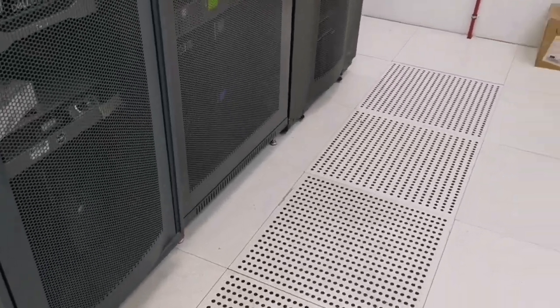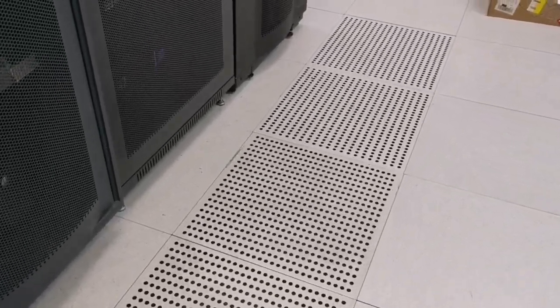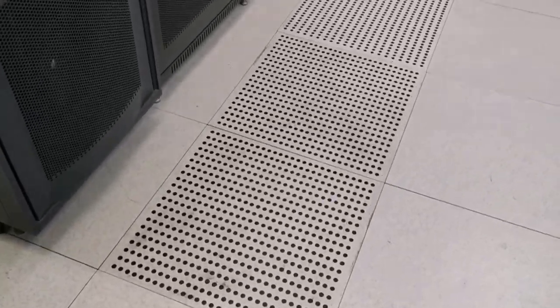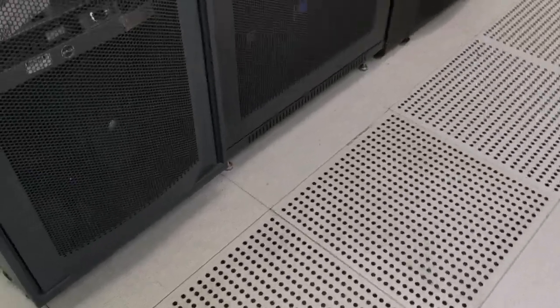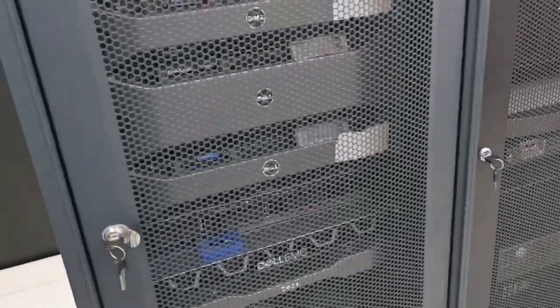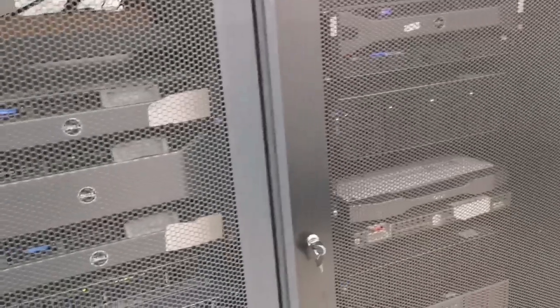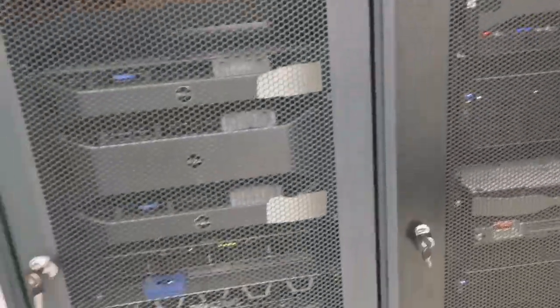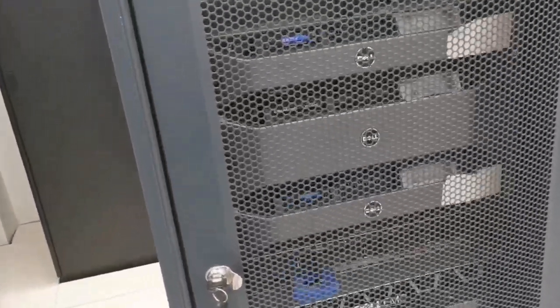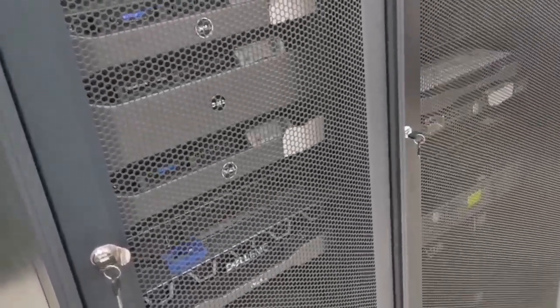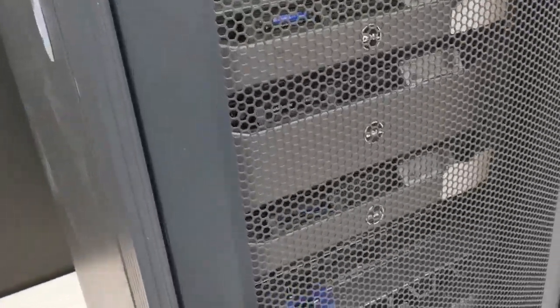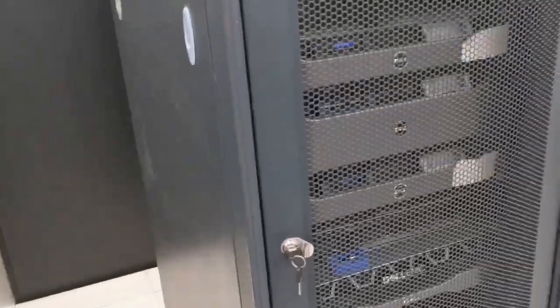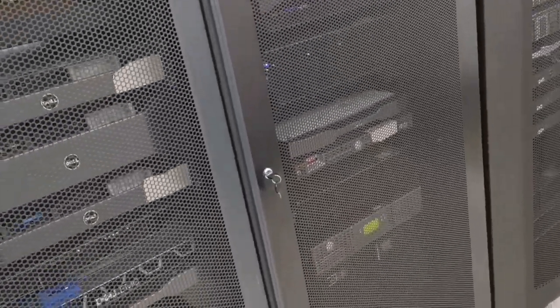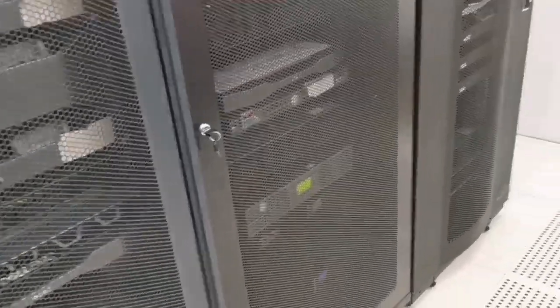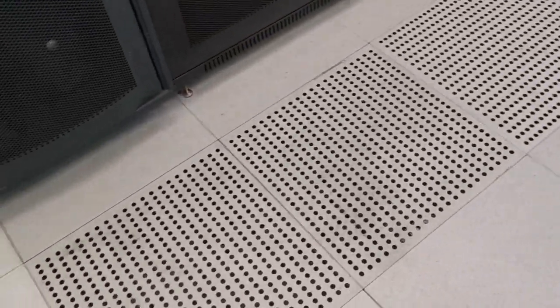As for the cooling of the server room, the cold air comes out from underneath through the holes in the raised floor. As you see here, the cold air goes up. The servers will suck in the cold air in order to cool the server and the other equipment, of course. After cooling, through the fans of the servers and the equipment, the air will go out from the back of the cabinet as hot air. The ACs will take this hot air and cool it again, and then send it back from underneath in order to complete the circuit.